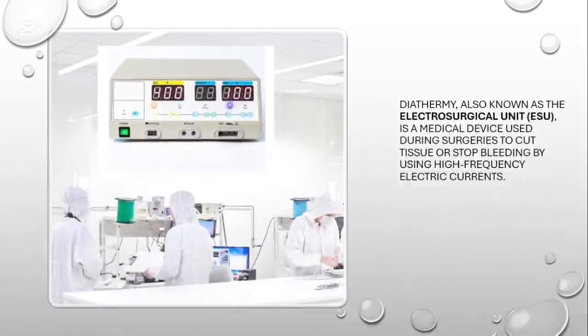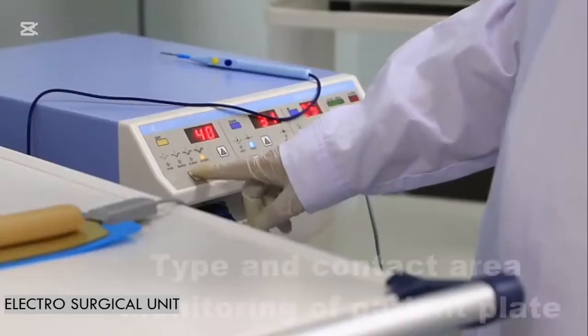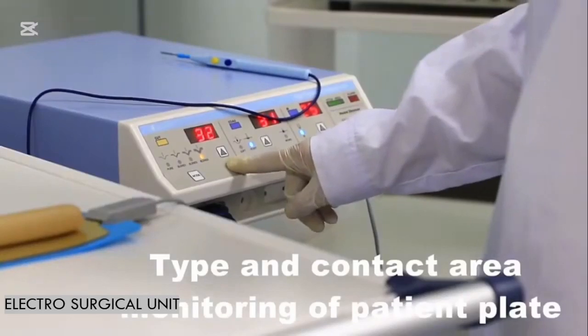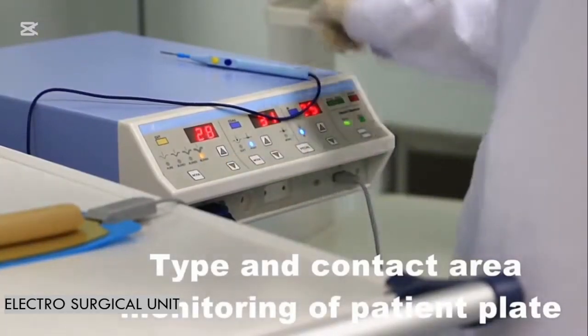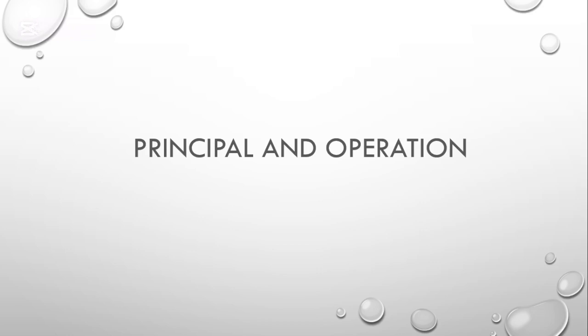Introduction. Diathermy, also known as the electrosurgical unit (ESU), is a medical device used during surgeries to cut tissue or stop bleeding by using high-frequency electric currents. The ESU passes high-frequency alternating current through the body tissues, which causes the tissue to heat up. This can either cut the tissue if it's very intense or coagulate, stop bleeding by clotting the blood. Now let's go through its principle and operation.